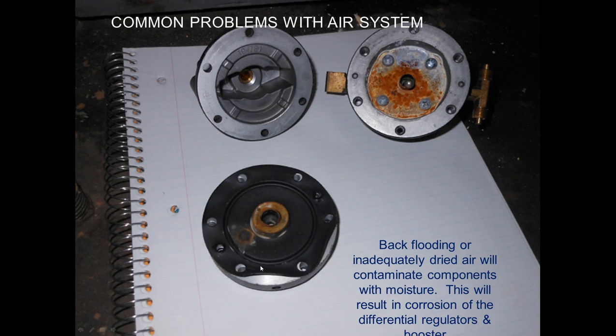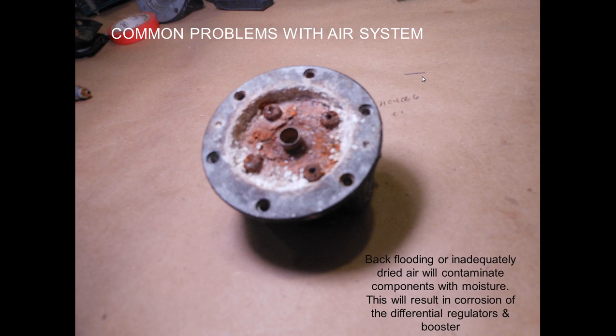Here's what it looks like when you have problems with components. This is a disassembled booster assembly. You can see significant corrosion and debris. This booster wasn't working anymore. This is another, actually this is the bottom of an intake regulator, and you can see that it is just badly corroded.